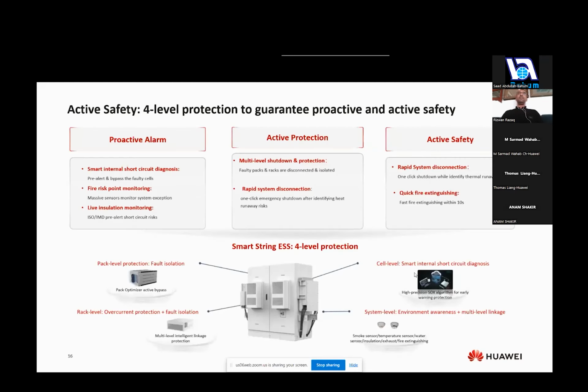So as I explained, from an active safety level perspective, we've got 4 levels of protection in order to guarantee proactive and active safety. So firstly, we've got the pack level protection, which is a pack level active bypass. So as soon as there is a temperature fluctuation in the battery packs themselves, we can limit the usage of that battery pack. Second is your rack level overcurrent protection, with multi-level intelligent leak linkage protection built inside the PCS. Number 4 is the cell level internal short circuit diagnostic. So with the high precision state of charge algorithm, there is early warning protection.